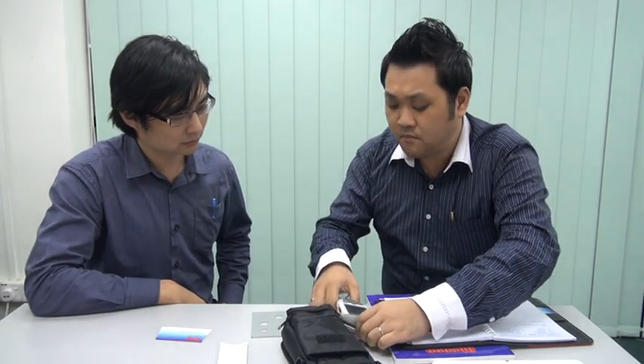And in the market, no matter Elcometer or another well-known brand, Fischer, their accuracy is controlled at 1 to 3%, also based on how they perform the calibration, either 1-point calibration or 2-point calibration. But on our side, we control at 0.75% accuracy tolerance. So for this item, we definitely have the most accurate coating thickness gauge in this market at this moment for the portable type. Do you want me to share more information about ElektroPhysik?